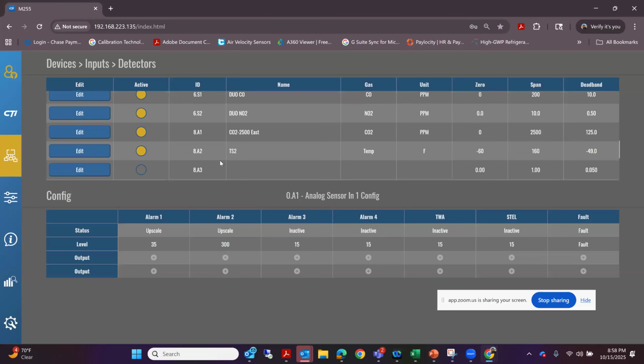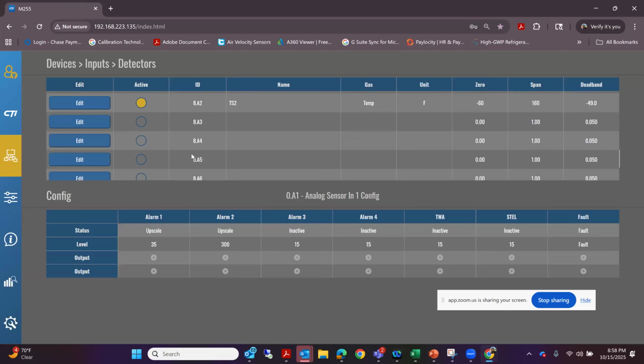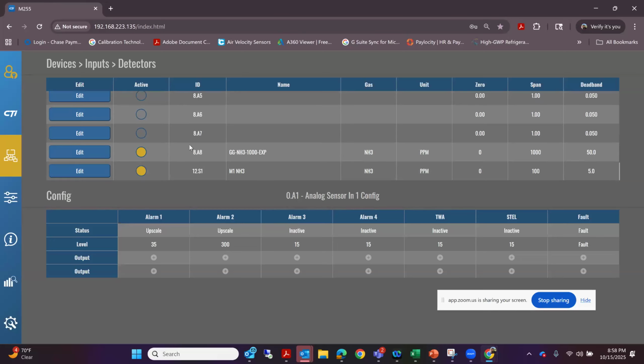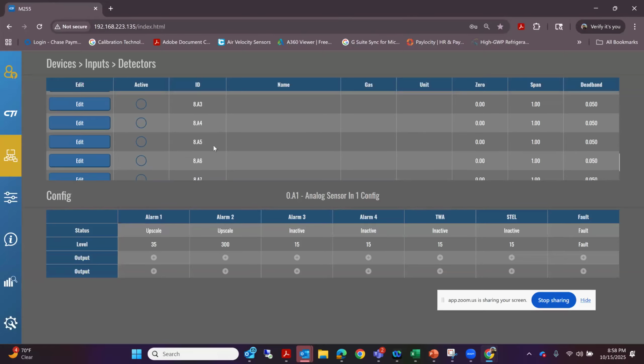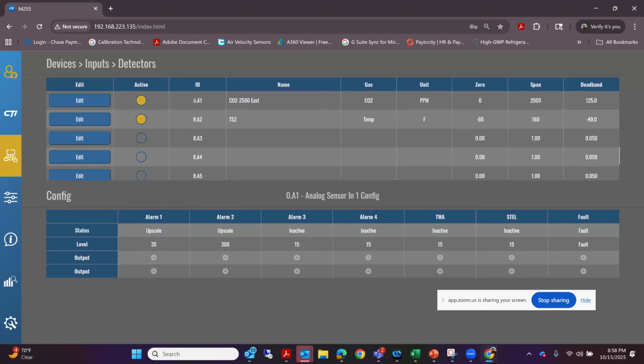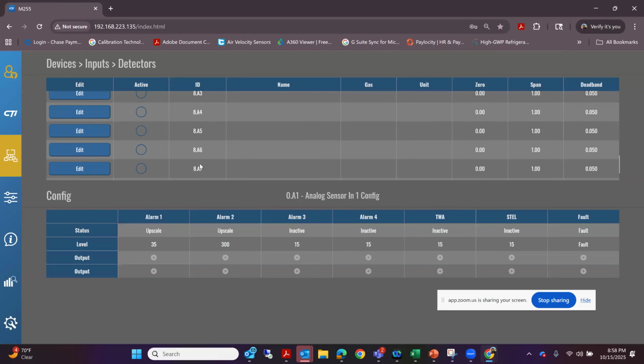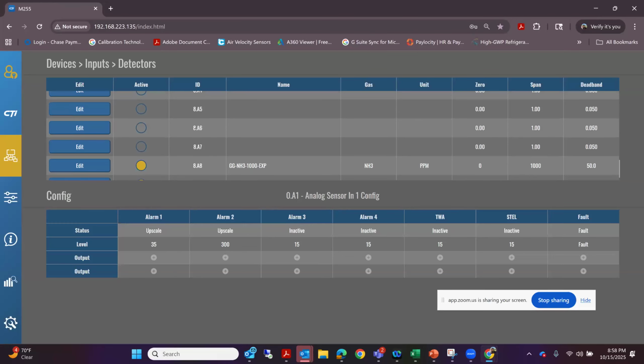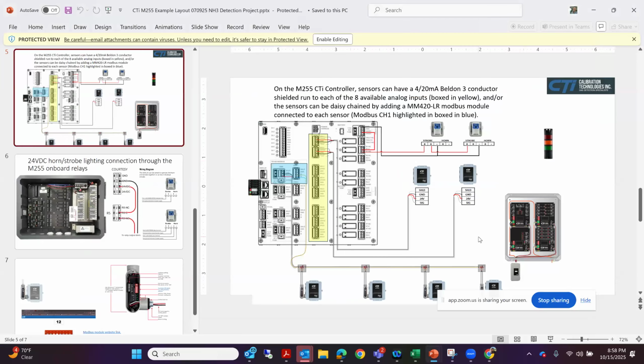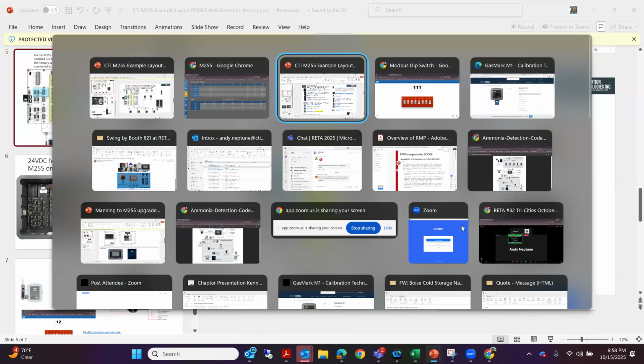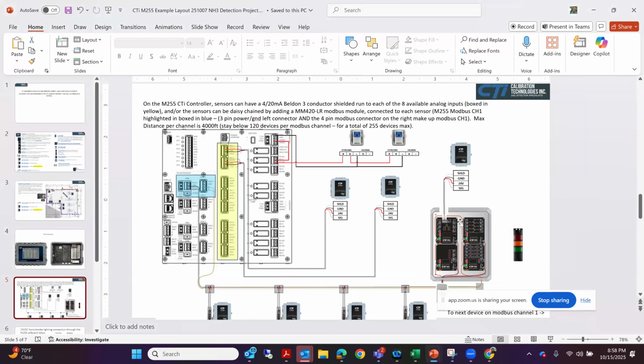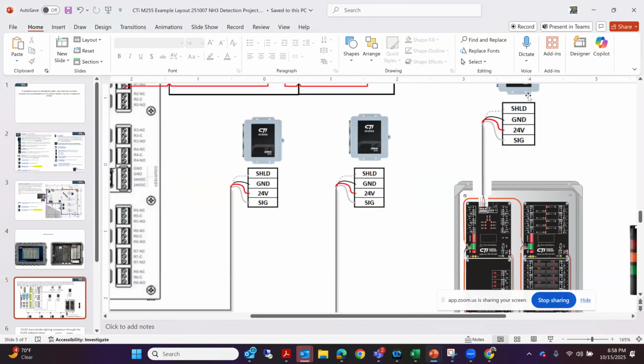And then, or excuse me, when you see these numbers on them, you know that this is an address sensor. So for instance, this is an analog input board. And so there's A1 through A8 analog input. So this board would be like what you're seeing out here on that example where that sensor was tied into it. So it would look like this right here. So that would be an analog input board right there, because we got a 4 to 20 sensor going right to one of the 8 inputs of that board. So that's what it shows up as on the controller.